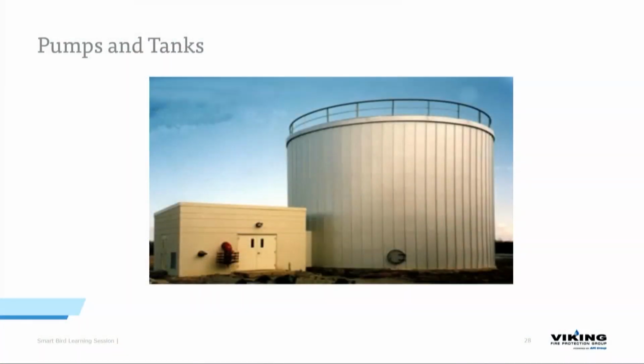So again, we've got access to the fire pump room here. That's that test header right there where we test the fire pump. Fire department connection. For this little room, you still have to have a fire sprinkler system in that little room. The one thing that's missing on this, and it drives me kind of nuts, is there's no horn and strobe on the exterior of this building. That just kind of grinds my gears. So there is a missing component to this facility here.